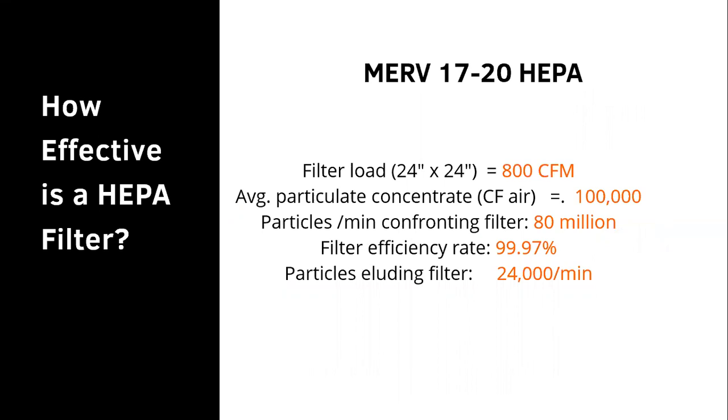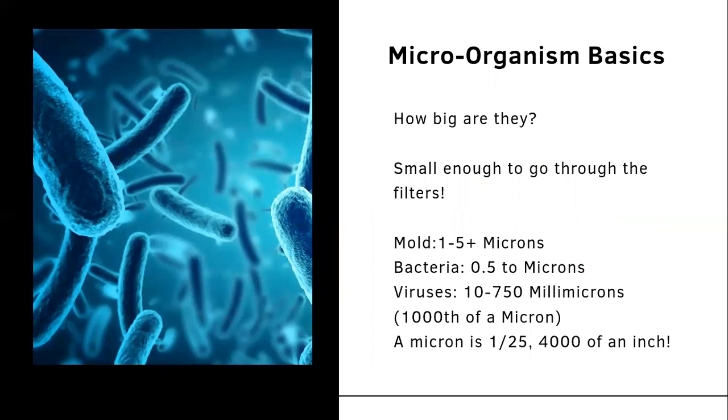MERV calculations demonstrate how effective your HVAC or HEPA filter is. Using a 24x24 filter example at 800 CFM: with an average particulate concentration of 100,000 particulates confronting the filter and 80 million total, even at a filter efficiency rate of 99.97%, 24,000 particles still elude the filter per minute. Microorganisms are small enough to pass through even HEPA filters, so HEPA filters alone are not enough to protect your building.